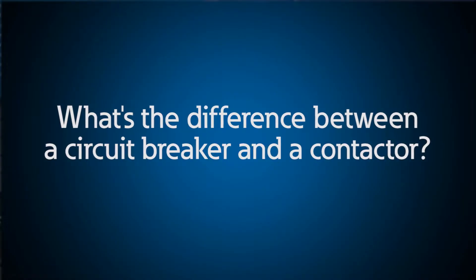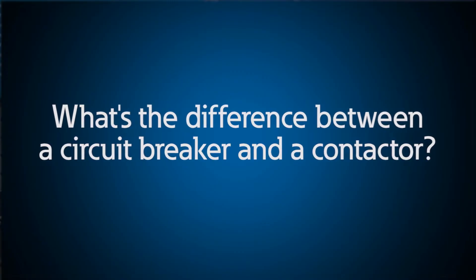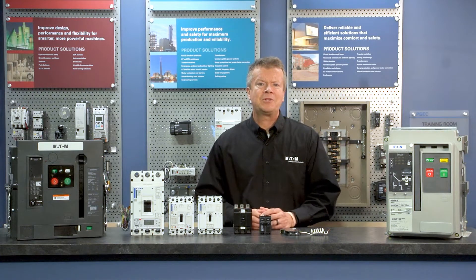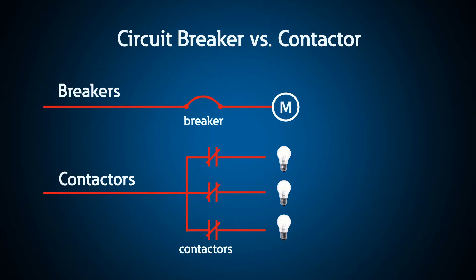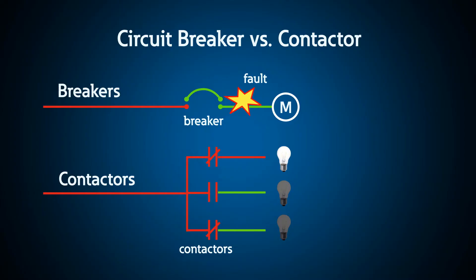Generally when you think of switching power circuits you may think of circuit breakers or contactors. So what's the difference? In general, a circuit breaker's primary function is to interrupt circuits during fault conditions or overload situations. A contactor is primarily used to turn on and off loads or control equipment. While breakers are designed to interrupt fault current, a contactor can trip during an overload condition, but if you tried to interrupt a fault with a contactor you would likely weld or damage the contacts.